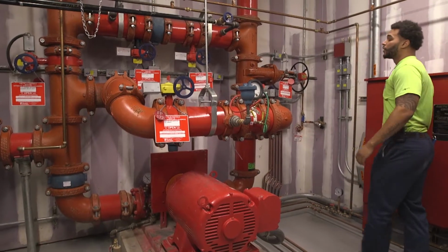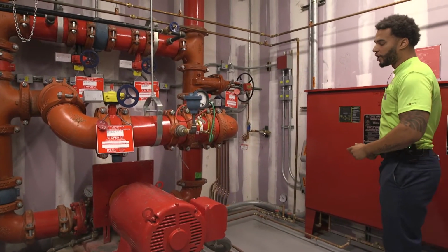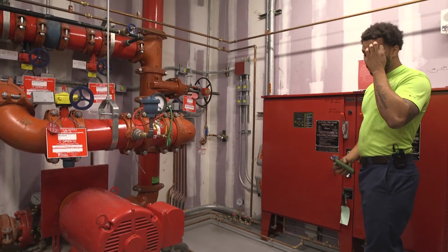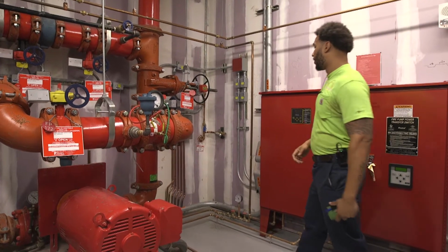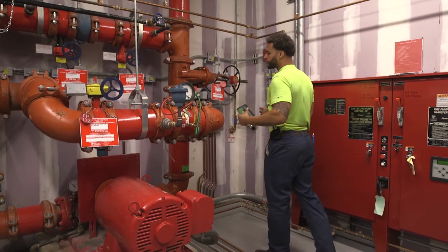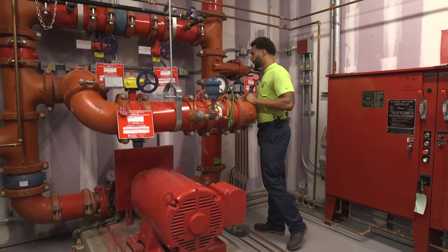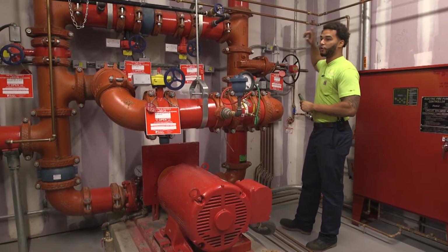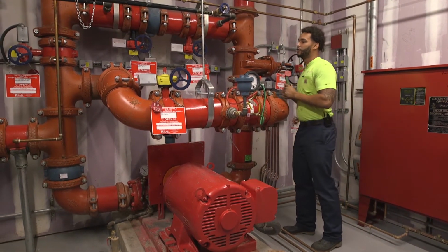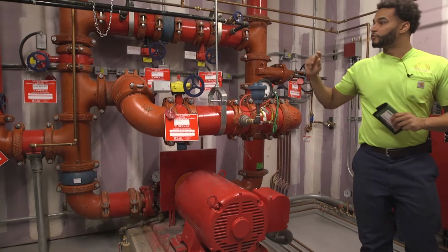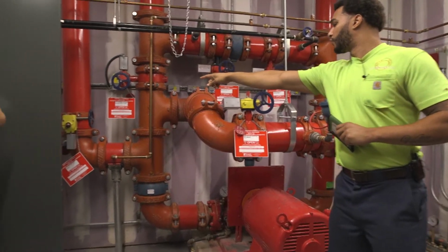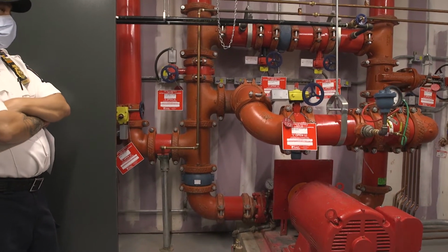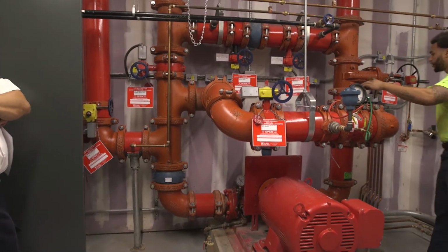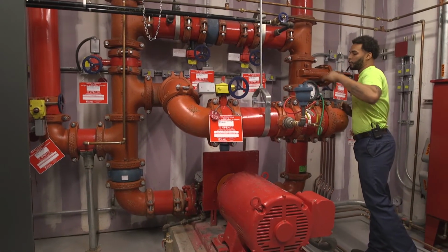So for testing, this fire pump requires annual testing that will be set up by your service contractor. So there are 2 ways this fire pump could be tested, or actually 3. One will be at the furthest point of your system. There should be 3 test headers. The second one will be right here through your fire pump test header. And the third way would be right here through your fire pump flow meter.